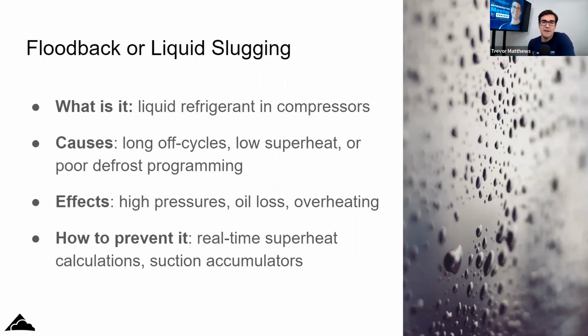Yeah, so really anytime a compressor is running and liquid refrigerant returns to the compressor, that's considered floodback. And it happens differently to different compressors. So say a semi-hermetic compressor, if you have really low superheat, and I've seen this tons of times, either the mechanical valve, the metering device, is not set up properly, or it has failed open, or something jammed in it, and liquid just continues to go even though it's supposed to close off and satisfy that evaporator. It makes it back while it's running, and then it starts to dilute the oil, and then it starts to wear parts in the compressor, wears the bearings, and then it reaches the point where you have a mechanical failure, which then turns into an electrical failure.